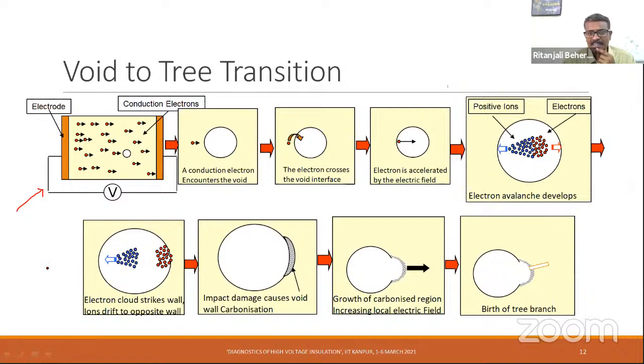And hence the short circuit takes place, or in other words, the partial discharge takes place. And once a partial discharge takes place, it bridges the gap, like this. It bridges the gap here. The potential difference between this end of the void and this end of the void becomes 0, and hence the discharge quenches by itself.